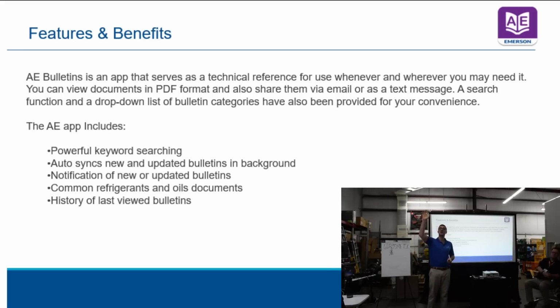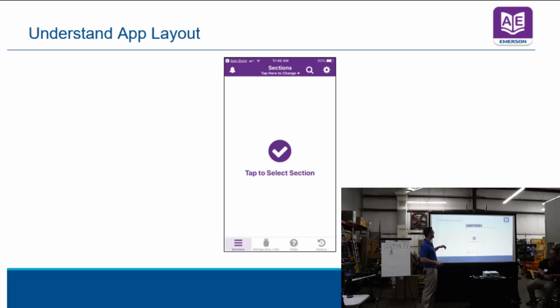If you're troubleshooting compressors and you're in the field and you don't have that information, how can you troubleshoot something if you don't know how it's supposed to work? You need this app, because this is how we design compressors. We use this and we give it to you to say, you cannot go outside these parameters or that compressor is going to fail. This is how you set up that low pressure control. You need a discharge check valve in the discharge line if you're using this much refrigerant, or in this application. Okay?